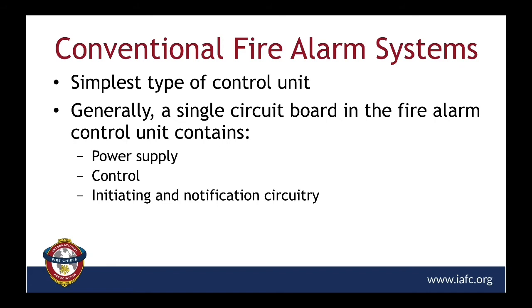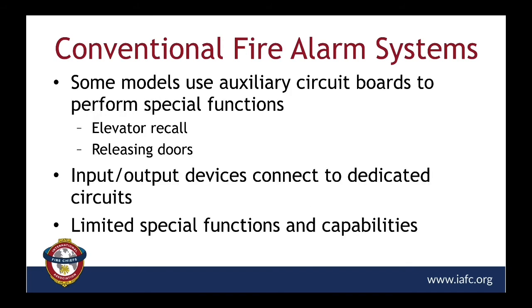So this is where those points that Richard talked about. Go ahead. So Dan, these are the units, right? If I'm responding out, where we might see something that says zone pull stations, and there could be maybe 4 pull stations, or zone smoke detectors, and there's like 5 smoke, right? When you're saying conventional, that's what they're going to kind of see, right? Exactly right. I'm going to show you a slide coming up here, Chief, where we'll be able to diagram that for you exactly. Great. But conventional is zoned is another excellent way to put it. We've just gone to the next slide here.